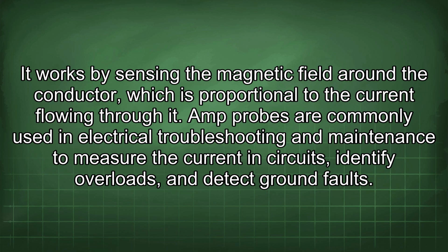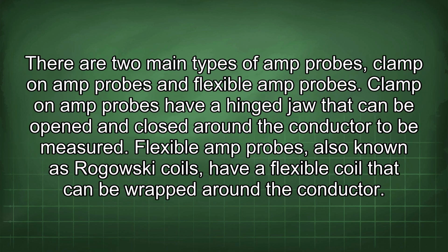It works by sensing the magnetic field around the conductor, which is proportional to the current flowing through it. Amp probes are commonly used in electrical troubleshooting and maintenance to measure the current in circuits, identify overloads, and detect ground faults. There are two main types of amp probes: clamp-on amp probes and flexible amp probes.